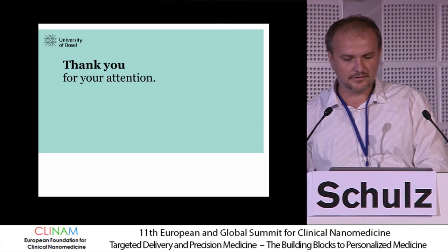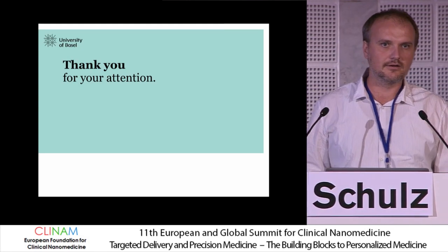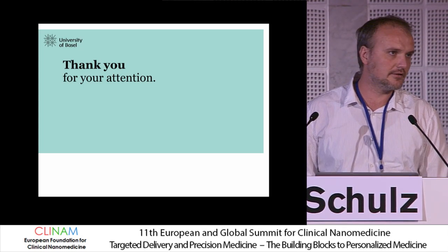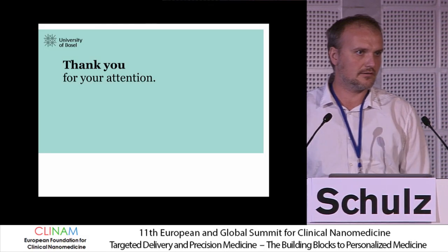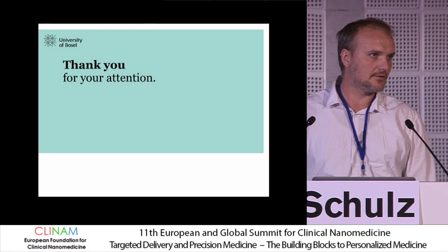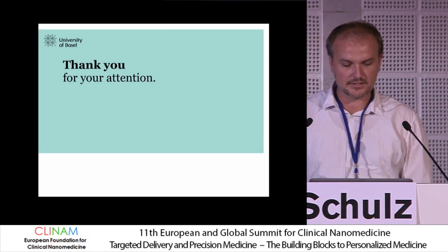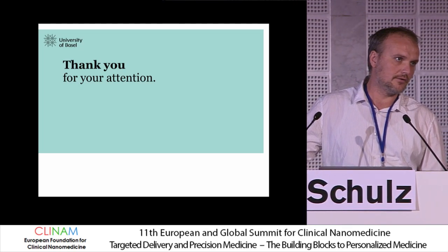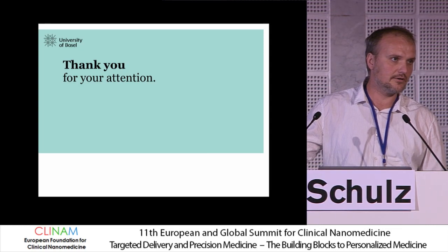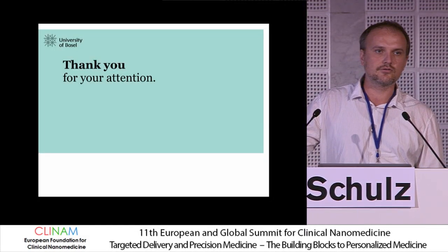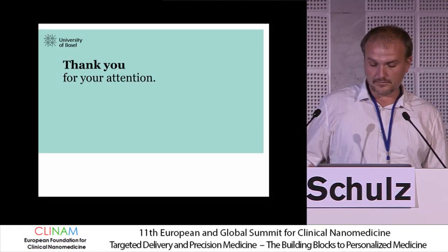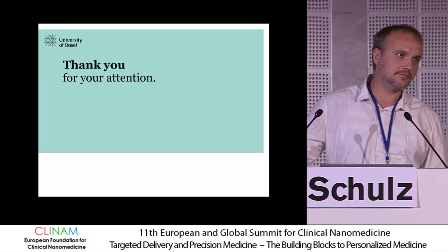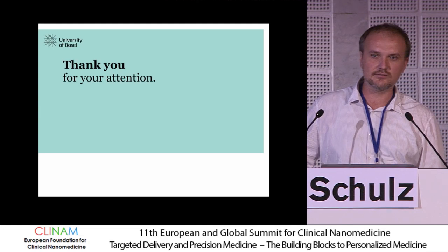Yeah. So first to the second part maybe. It doesn't change anything. Especially as this tissue is embedded in paraffin, there's no problem with the X-rays. Also, most of the X-rays pass by; only some of them are attenuated by the specimen. About the scan times, they are between 15 minutes for a normal, fast scan, where it's pretty noisy but still you can see something. And if you go down in resolution, then you could get scanning times of around 10 hours. The smallest pixel size you can get is 200 nanometers.